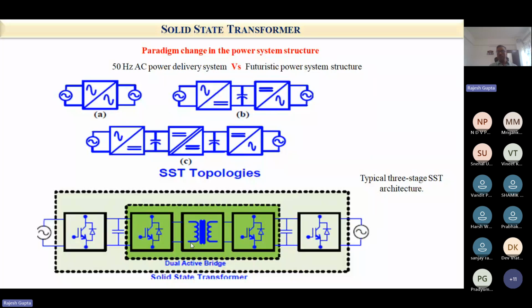So if I'm calling it a transformer, whether solid state transformer or not, I must have a transformer. Only thing, I shifted from low frequency 50 hertz to high frequency, 40 kilohertz or 65 kilohertz, depending on how the converter switches are operated. This is purely a power electronics concept: I have decoupled the 50 hertz AC from the 40 kilohertz AC with the help of these converters, and therefore I am using a very small transformer which fits within a box size. That's the advantage of using a solid state transformer.